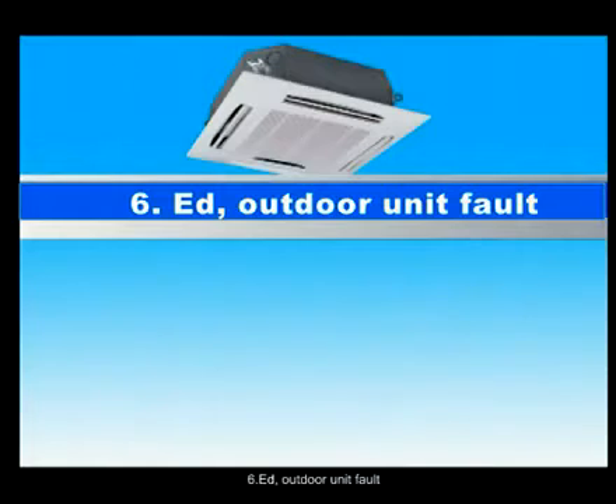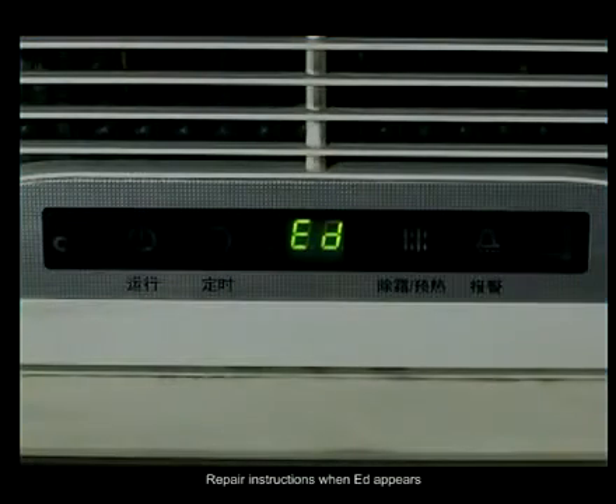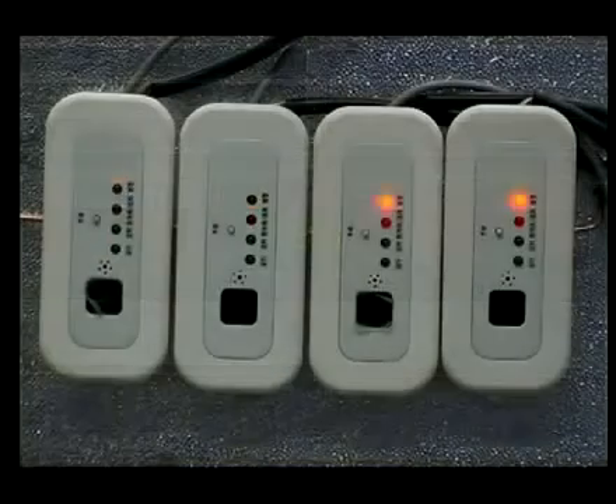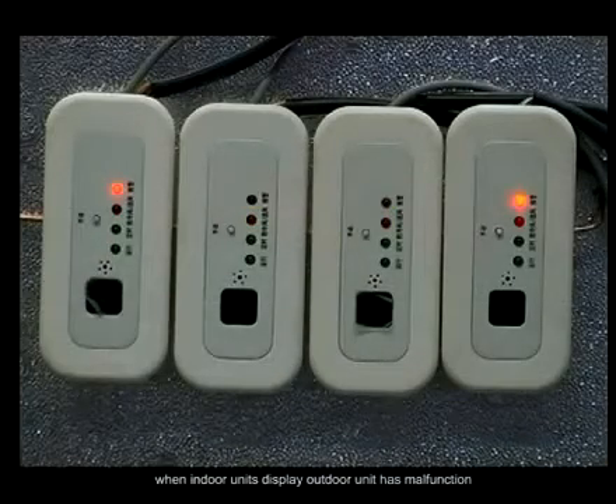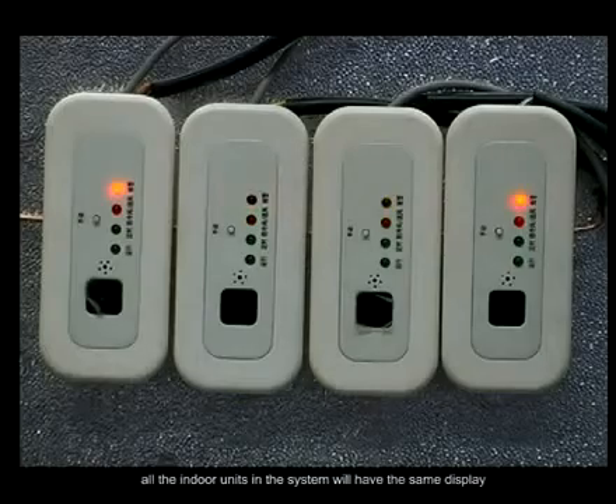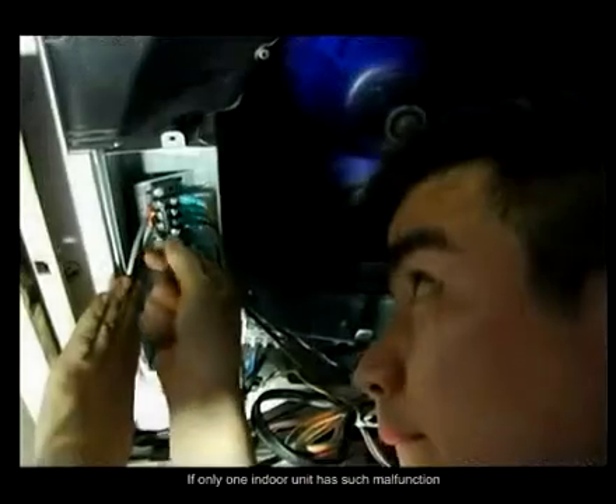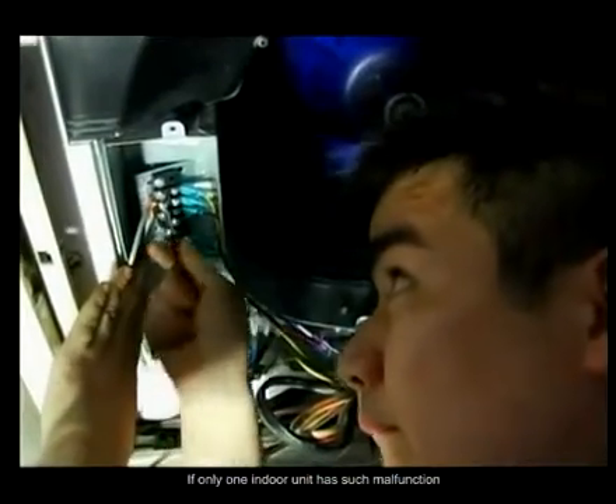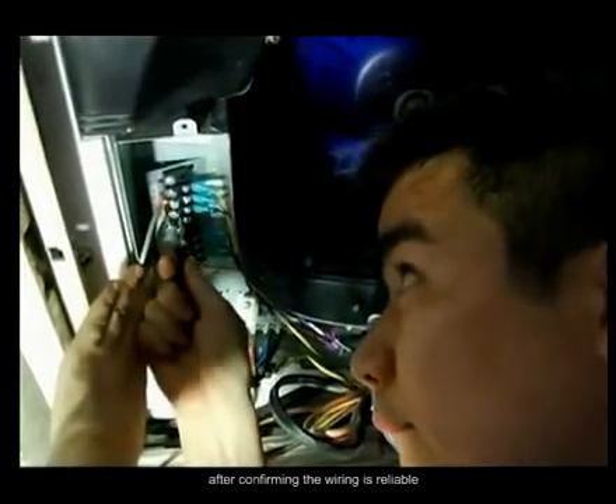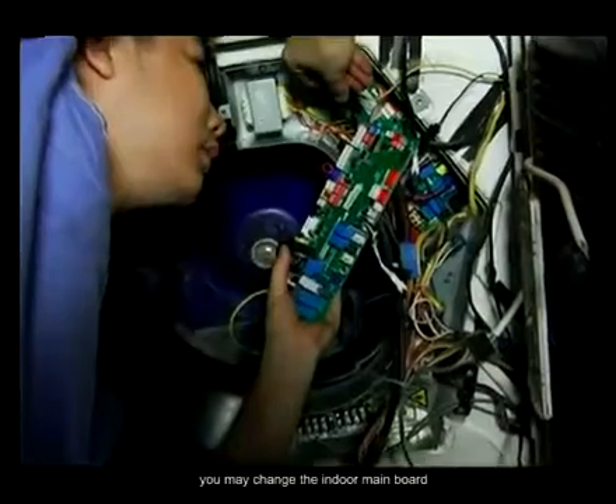6. ED, outdoor unit fault. Repair instructions when ED appears. When indoor units display that the outdoor unit has a malfunction, all the indoor units in the system will have the same display. If one indoor unit has such a malfunction, after confirming the wiring is reliable, you may change the indoor main board.